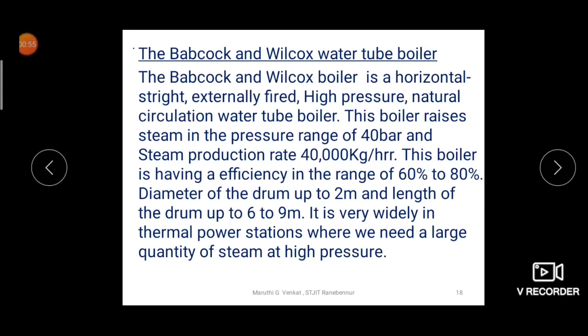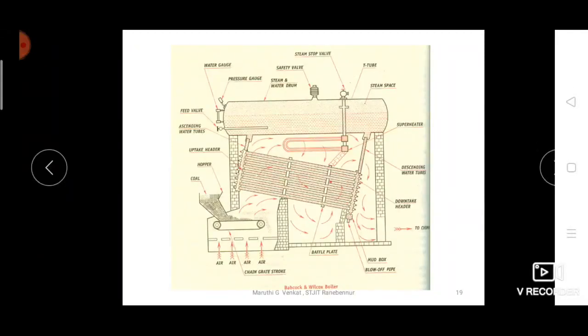Using this boiler, we can generate steam up to a pressure of 40 bar, which is why it is called a high pressure boiler. The steam production rate is 40,000 kg per hour. The boiler efficiency is in the range of 60% to 80%. The drum diameter is up to 2 meters and the drum length is 6 to 9 meters. Because of these specifications, it is widely used in thermal power stations, which require large quantities of steam at high pressure.